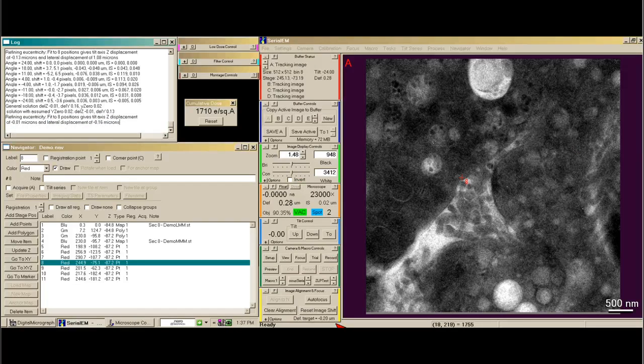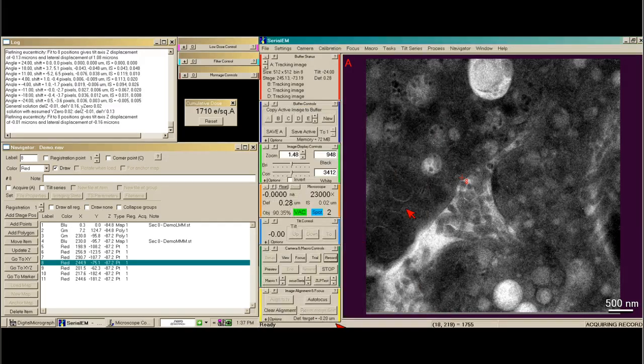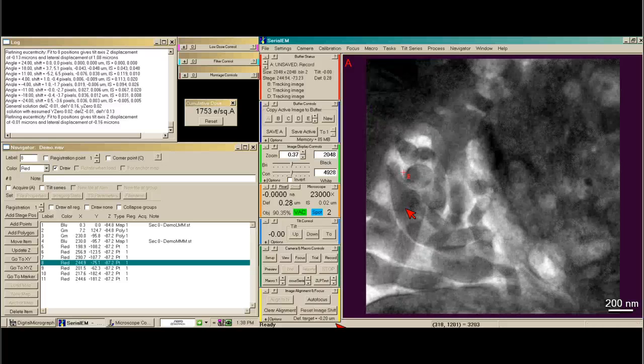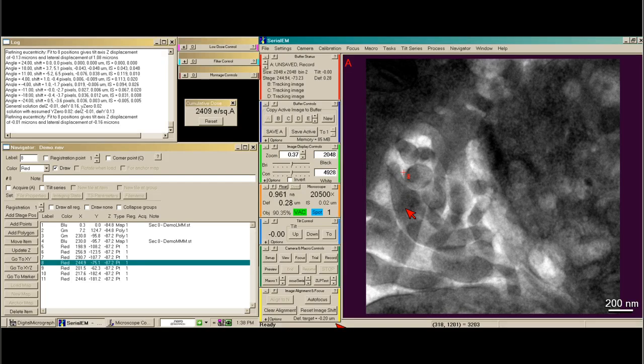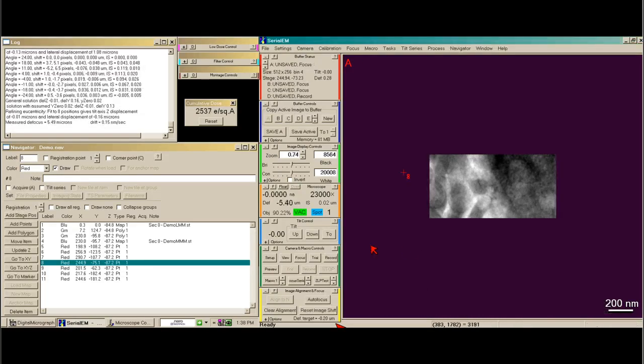Now I need to just double-check my final imaging parameters. I go to the setup, check that my record is binned by 2, and that I'm happy with the exposure time and the drift settling time. I take an image and see what it looks like. My purpose is to make sure that I have plenty of counts, that I'm in focus, and that it is the area of interest. We don't have enough counts and we are not in focus, so I'm going to increase the beam intensity, do a quick autofocus, and take a record image.